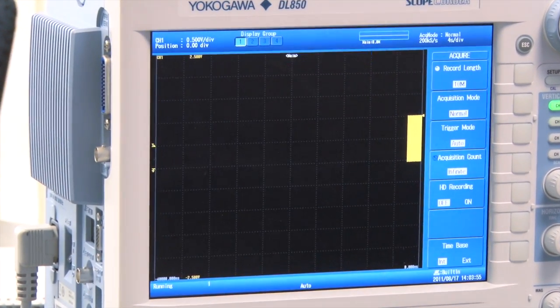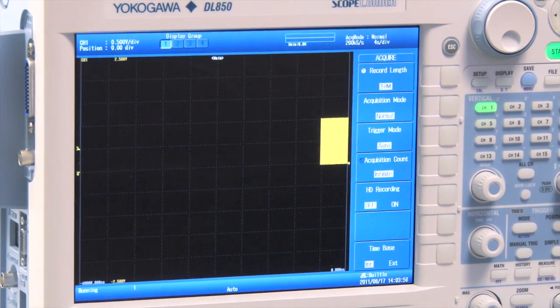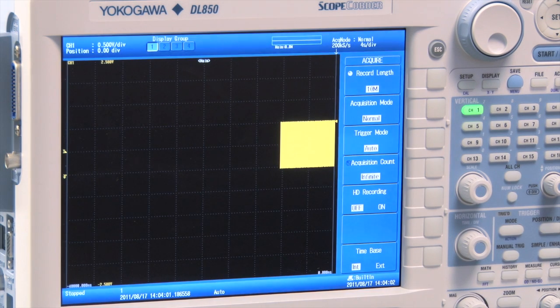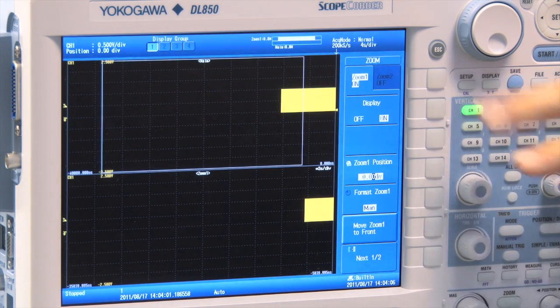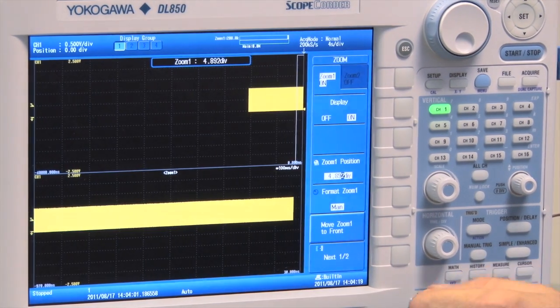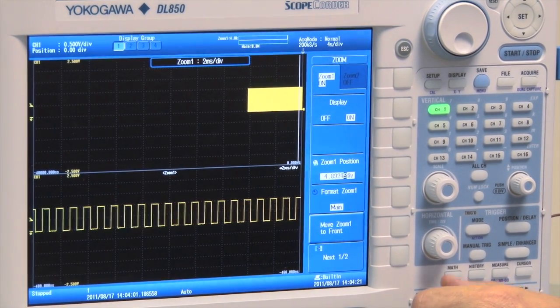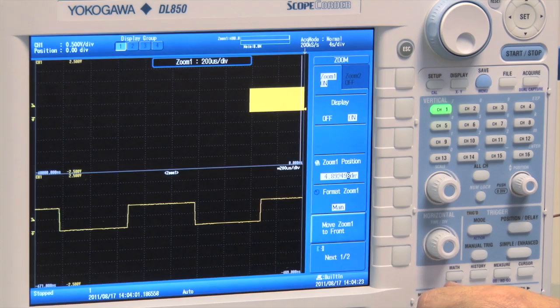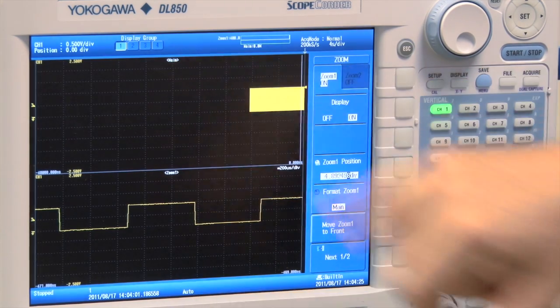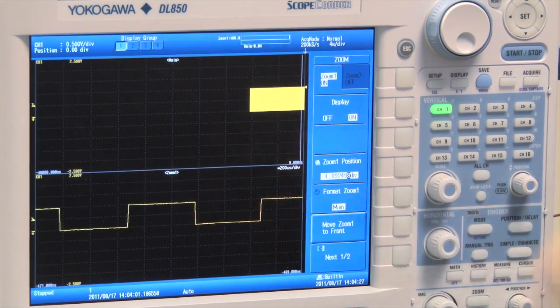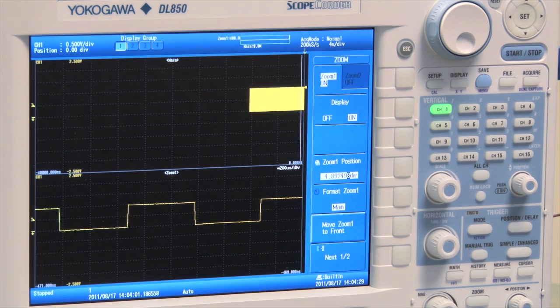So right now we're at four seconds per division. Now if I stop that and want to look at any information in that, we do have zoom windows. A nice feature about the instrument itself is with all the information it takes, it can really resolve down to a fine point. So up here we're on four seconds per division, down here we're on 200 microseconds per division.